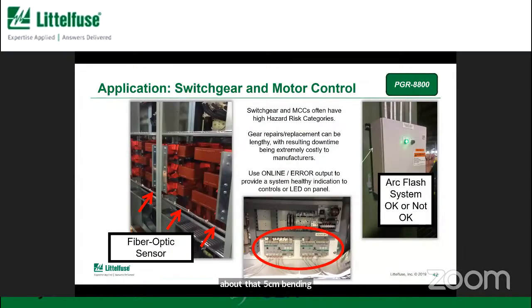Another area: here in this piece of switchgear, they have all the bus work connected through some insulating points, and all the bus work is in the back of the equipment. The fiber here, they just strung it along a structural member on the back so that it's able to see if there's any loose connection that starts to generate an arc. So the fiber sensor is great at providing coverage for a long distance.